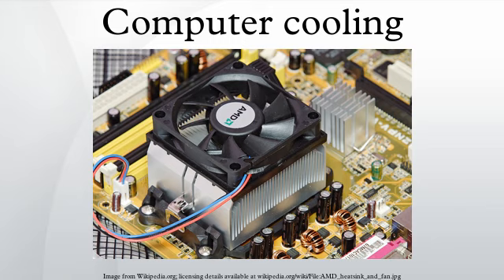This type of system suffers from a number of issues but, mainly, one must be concerned with dew point and the proper insulation of all subambient surfaces that must be done. Alternately, a new breed of cooling system is being developed, inserting a pump into the thermosiphon loop. This adds another degree of flexibility for the design engineer, as the heat can now be effectively transported away from the heat source and either reclaimed or dissipated to ambient.